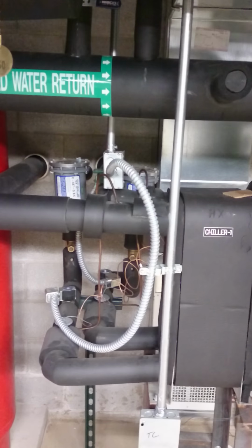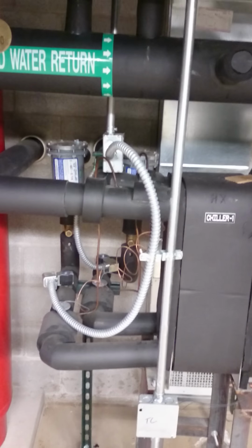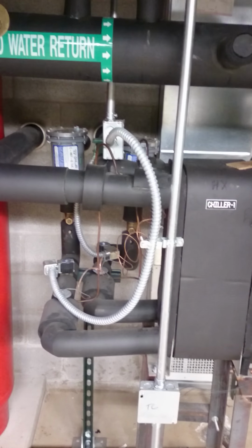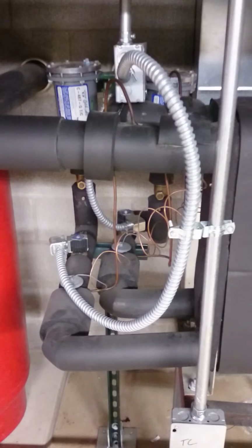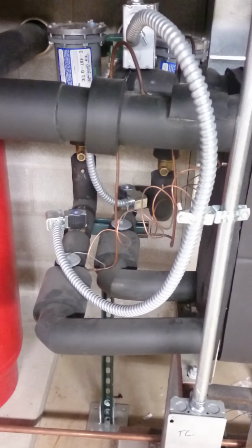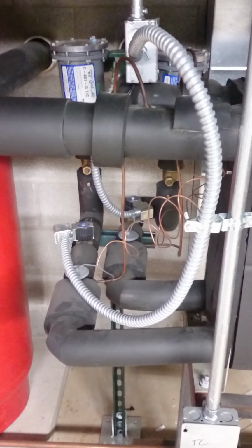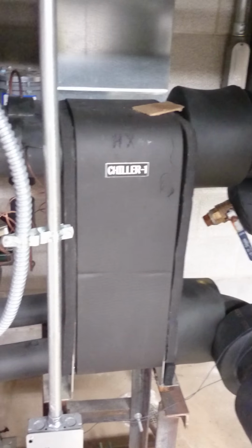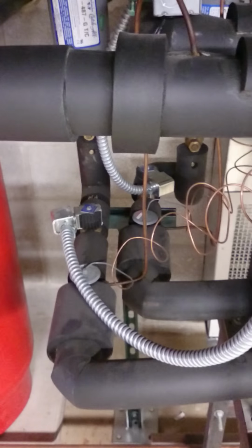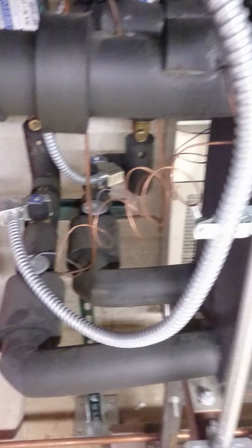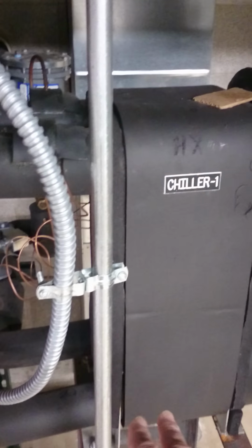Outside we have a Trane 40-ton chiller, and the chiller is located outside, and we've got our refrigerant lines coming to a remote evaporator. We're using a flat plate heat exchanger as our evaporator. So we've got our two liquid lines entering in the TXV. So this piping here would be the beginning of our evaporator. So then we have a refrigerant to water heat exchanger. So we have pumps that are moving water through the heat exchanger here.